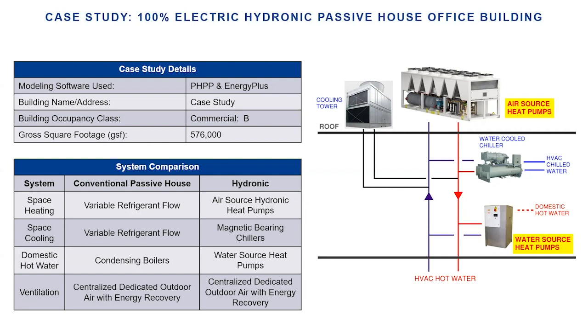So in our base case here, this is the previously discussed conventional passive house building with a VRF system for heating and cooling, gas boilers for domestic hot water, and energy recovery ventilation. In our hydronic case, we substituted in air source heat pumps for space heating, high efficiency magnetic bearing chillers for cooling, and water source heat pumps for the domestic hot water. And we also have the same high efficiency energy recovery ventilation. So the system configuration on the right here is representing the hydronic case in this case study.